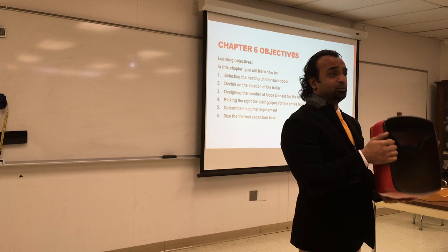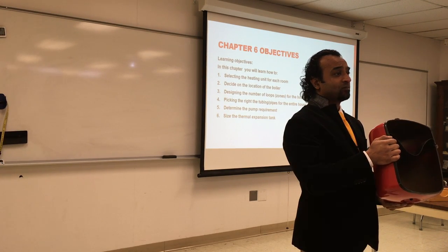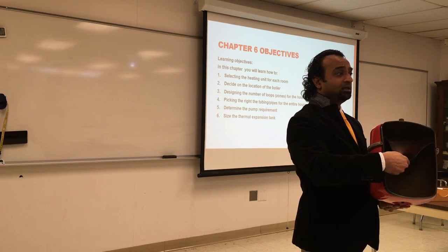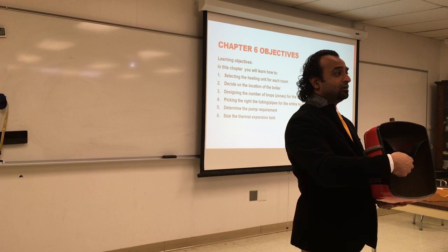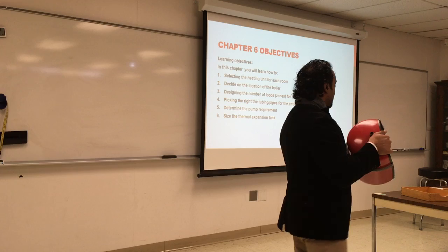I've seen some steam systems with expansion tanks. No idea why. That's probably malpractice, because it is going to disintegrate over time from the heat, and eventually it will leak. So something to think about.